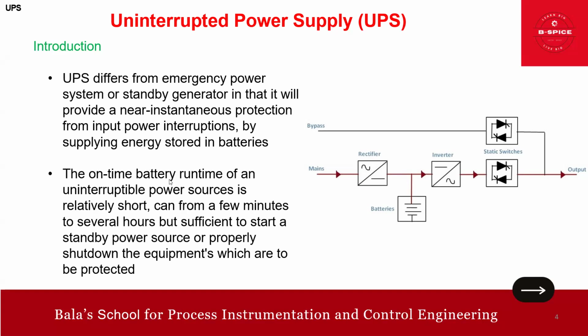The on-time battery runtime of an uninterrupted power source is relatively short, from a few minutes to several hours, depending on your configuration and design. Normally 3 to 4 hours is good enough, but it should be sufficient to start a standby power source or properly shut down the protected equipment. So this battery time depends on your specification or requirement.